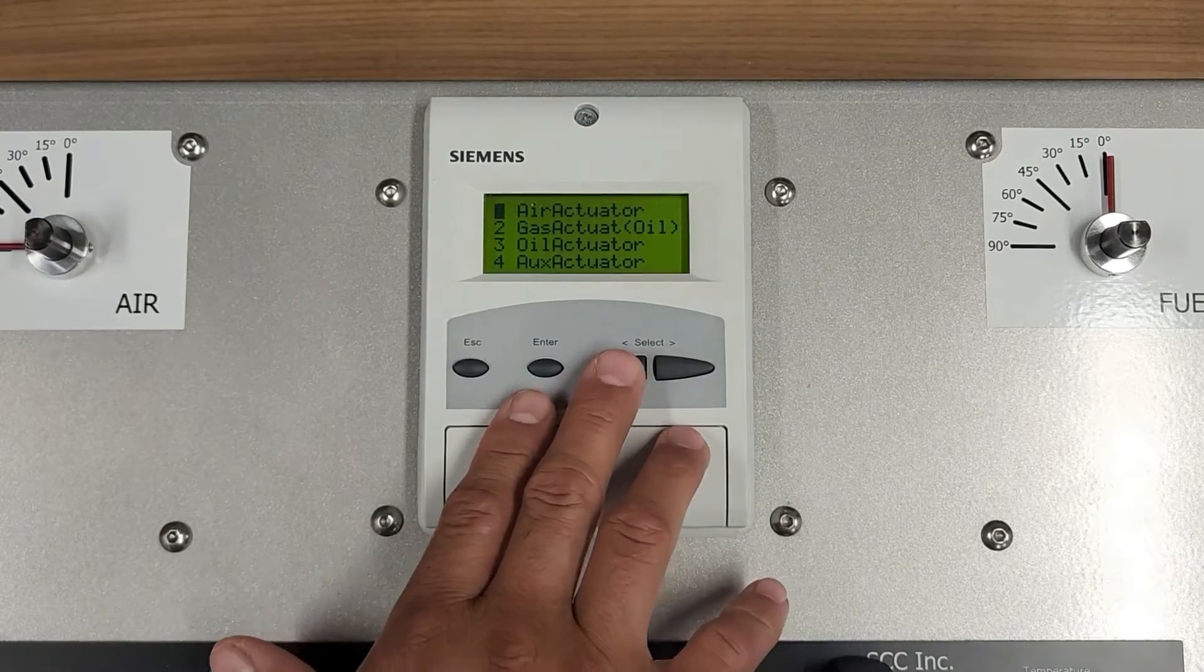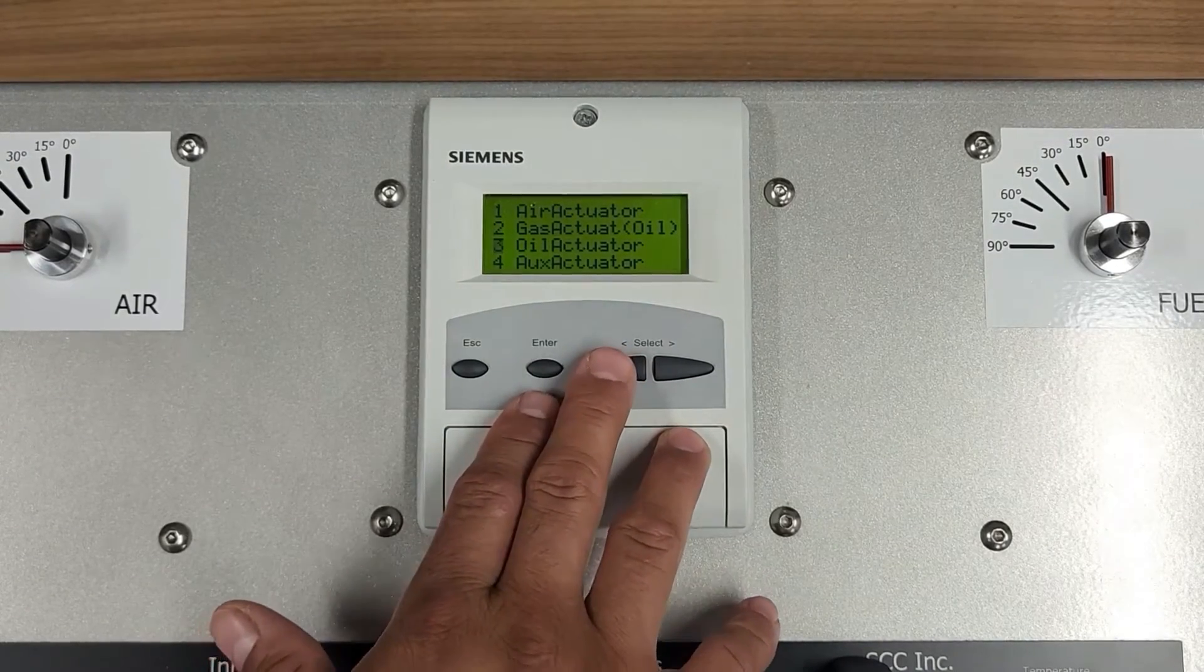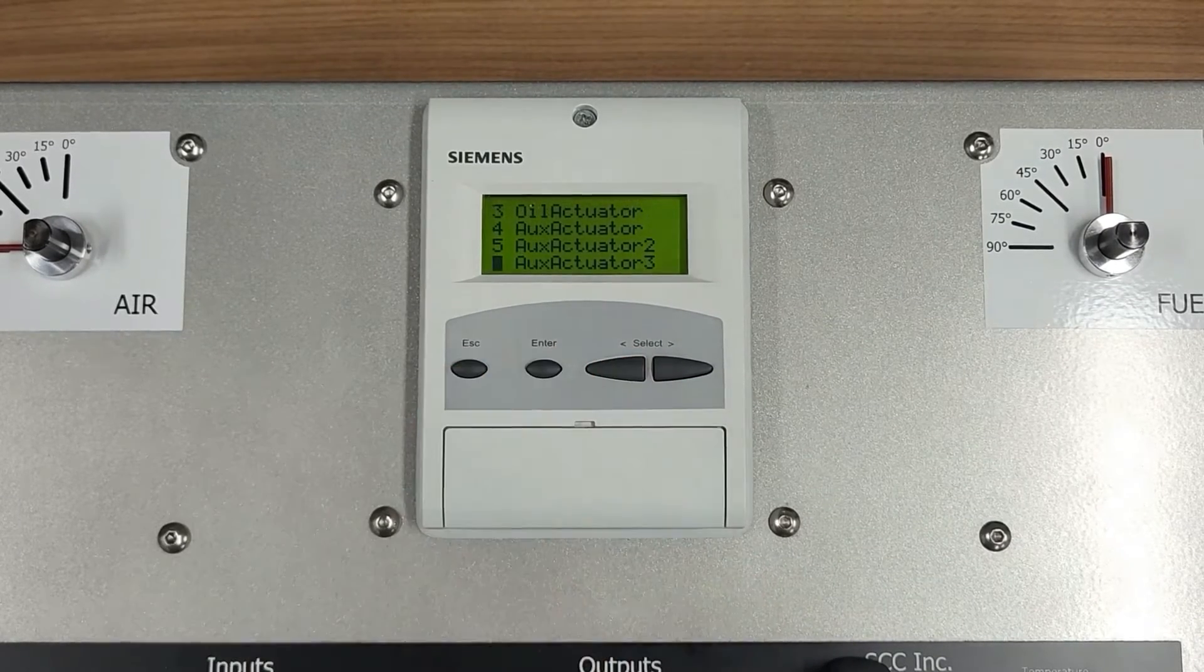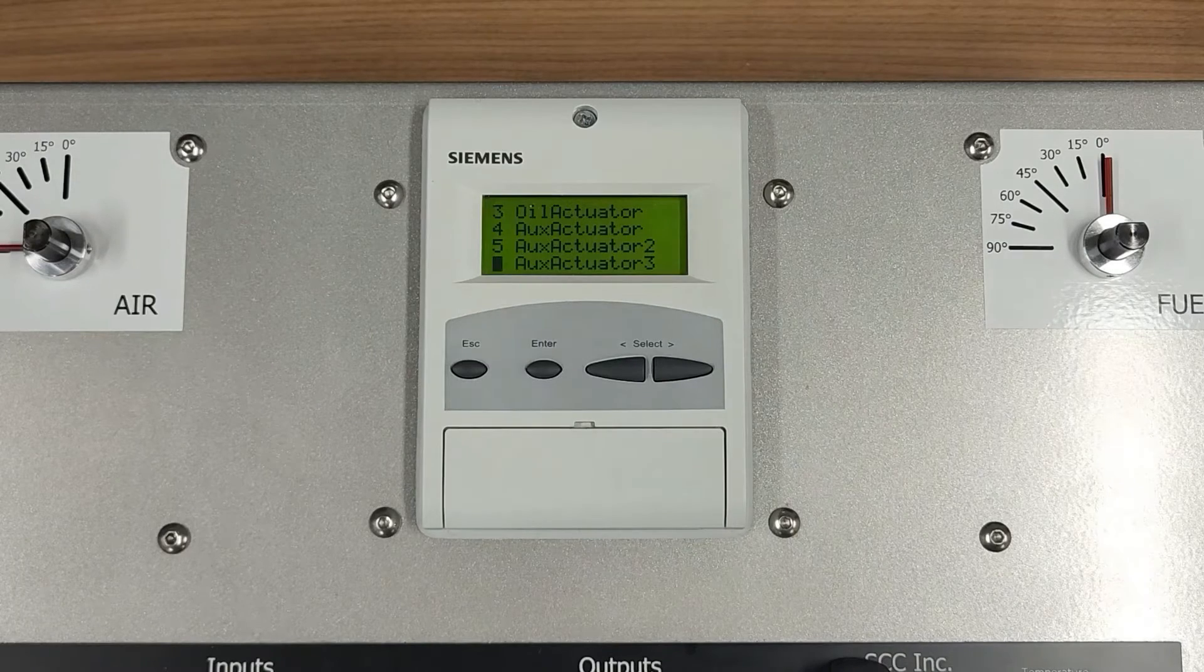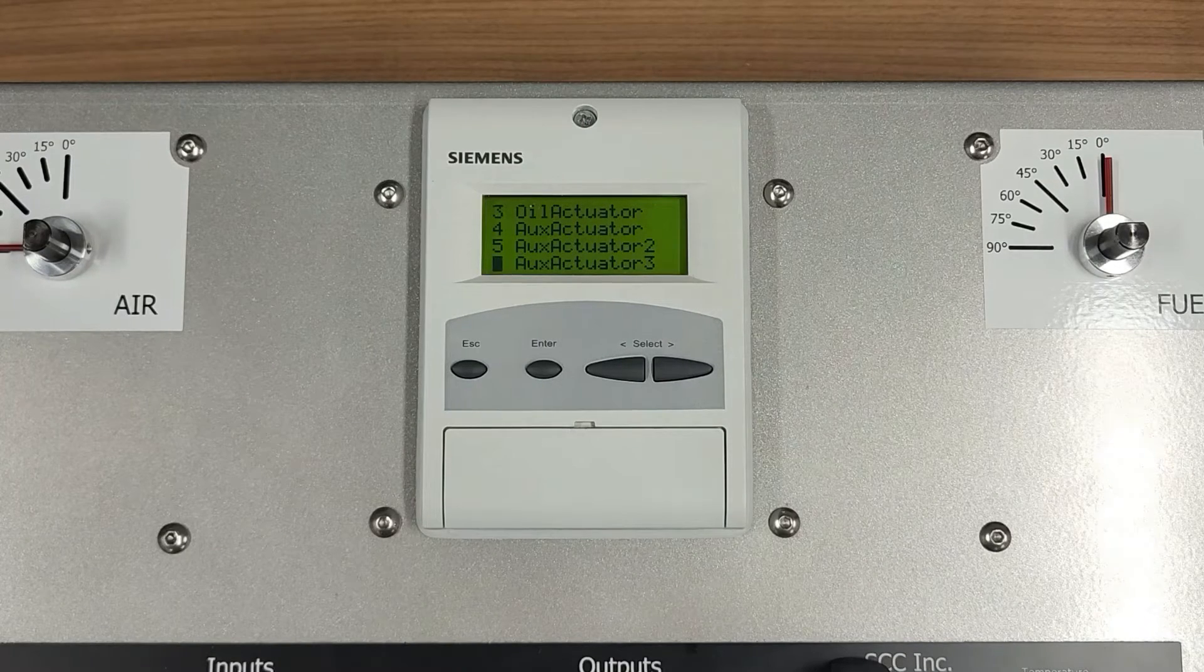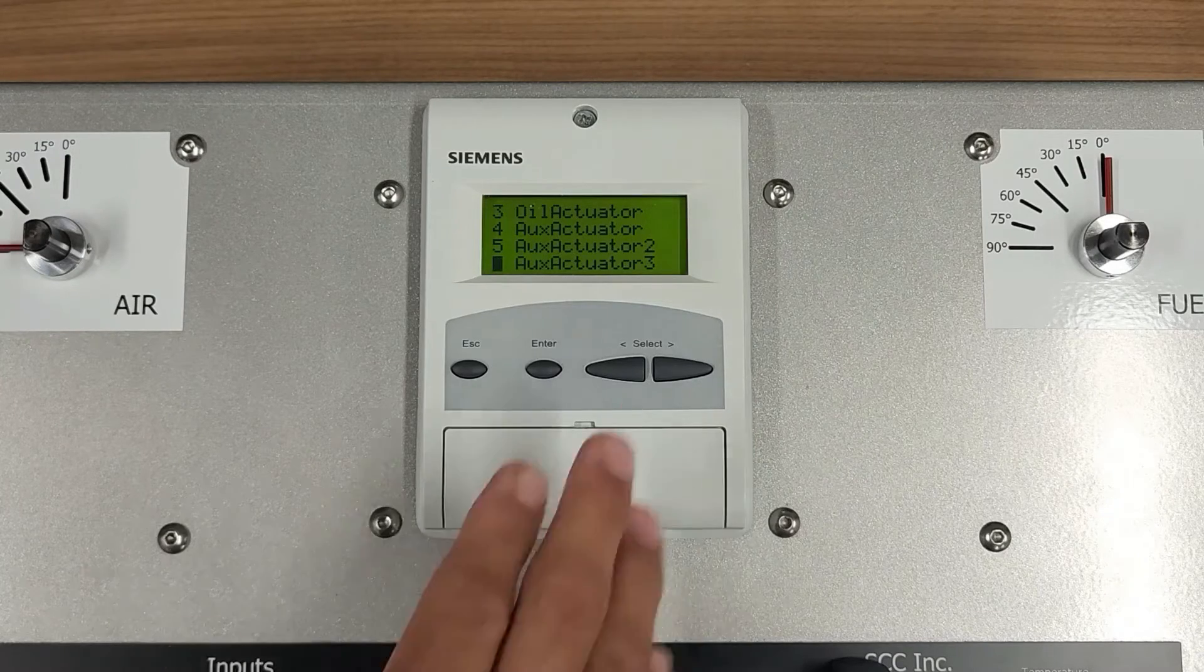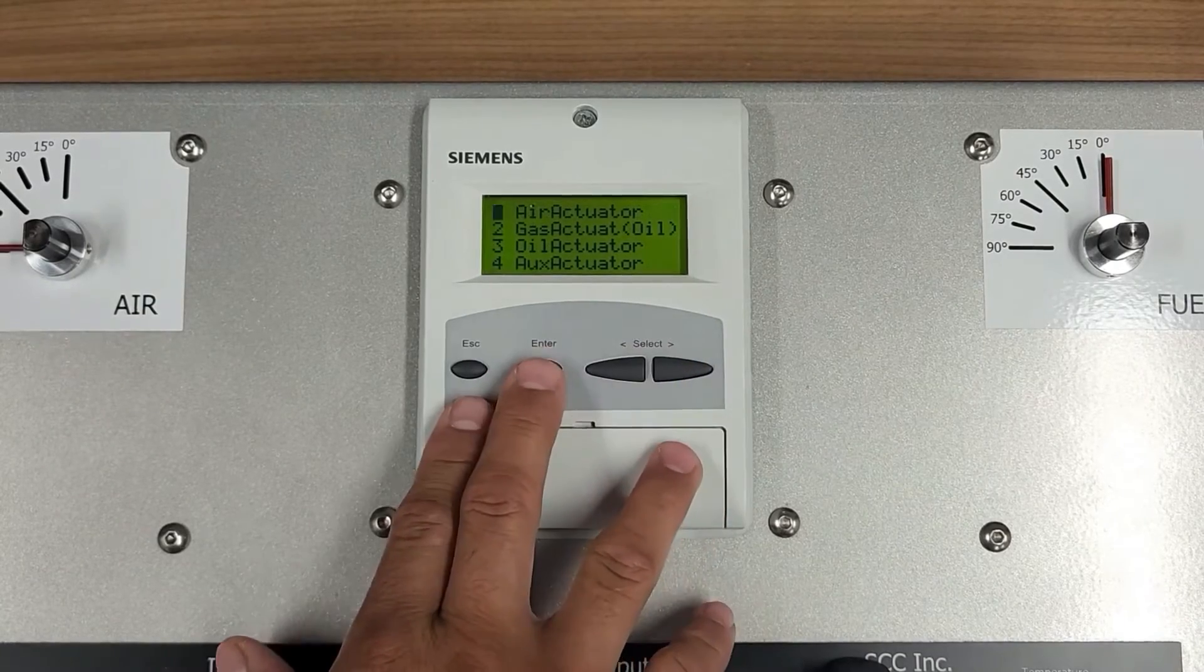One is going to be for Air Actuator, two for Gas Actuator, three for Oil Actuator, four, five, and six are going to be your Auxiliary Actuators. If you're using an LMV52 and Advanced FGR functions are needed, the FGR Actuator must be addressed as the Auxiliary 3 Actuator. In this example, we will be using number one, Air Actuator. Press Enter.